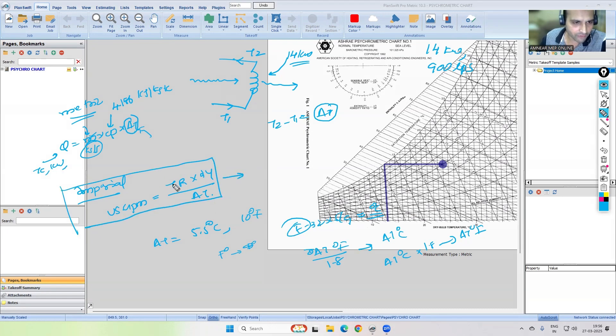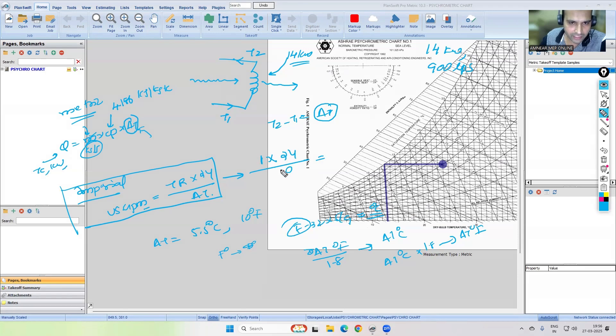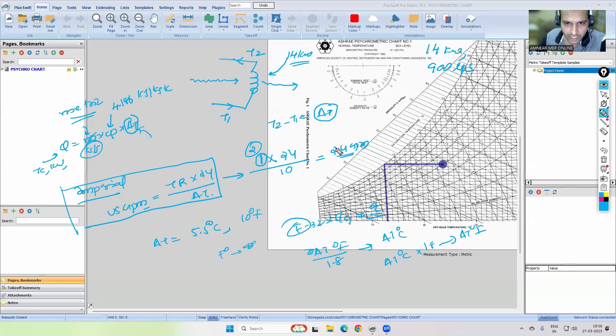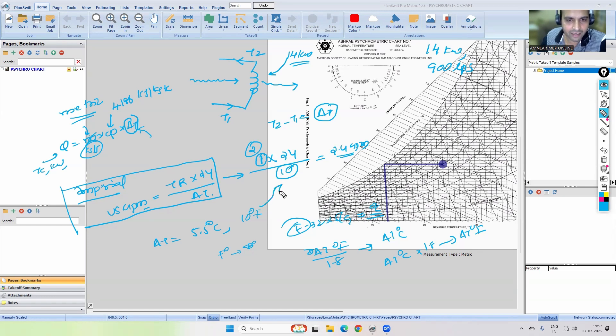In imperial standard, consider 1 ton of refrigeration. The chilled water flow rate formula is: GPM = tons × 24 / ΔT. If you consider delta T as 10 degrees Fahrenheit: 1 × 24 / 10 = 2.4 GPM. That's why 1 ton gives 2.4 GPM, and 2 tons gives 4.8 GPM — because the delta T considered is 10 degrees Fahrenheit.